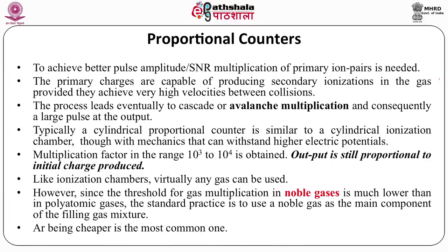However, since the threshold of gas multiplication in noble gases is much lower than in polyatomic gases, the standard practice is to use a noble gas as the main component of the filling gas mixture. Argon, being cheaper, is the most common gas used in proportional counters.